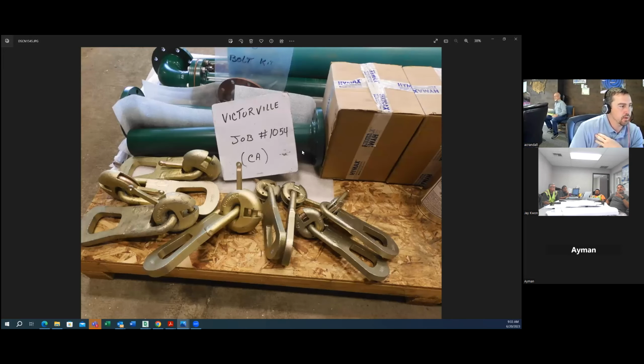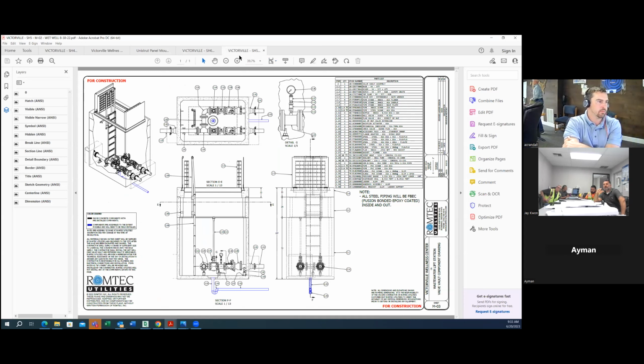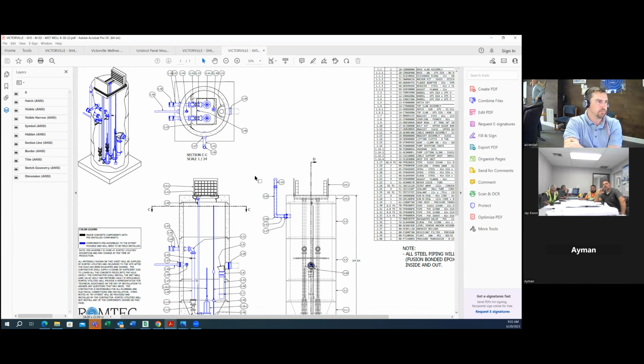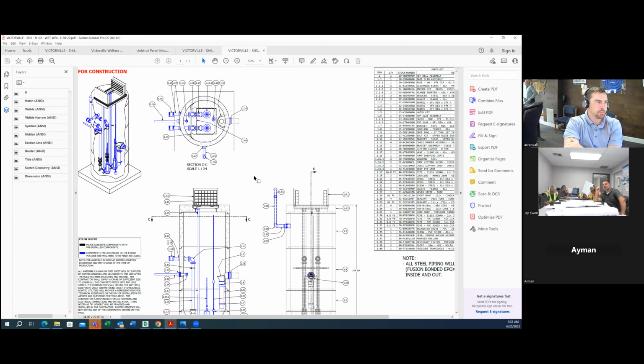Okay. I'm the electrical contractor. I just want to make sure I have my scope clear. Yep. The well will get delivered out there. It'll get set. After it's set, I will core two 2-inch holes, one 1-inch hole into the well, just a few inches below the top joint slab. And then I'll run those back to the control panel location, keeping the low voltage on the left side, power on the right side. We'll build a rack for the control panel. We'll run those conduits through some seal locks up into the control panel. We then will wait for the startup tech to come out.